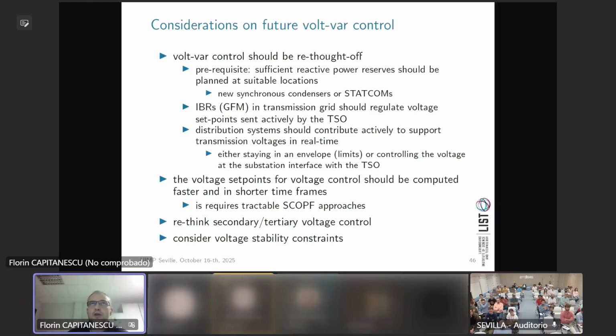It's not about how you control the voltage in real time, but how you get better set points to send to devices in the field. The prerequisite is that you need sufficient reactive power reserves to absorb and produce reactive power at suitable locations, and I think the methodologies I presented are very good for that.